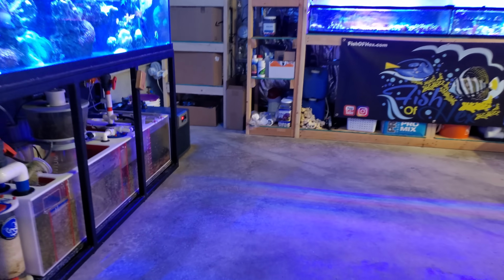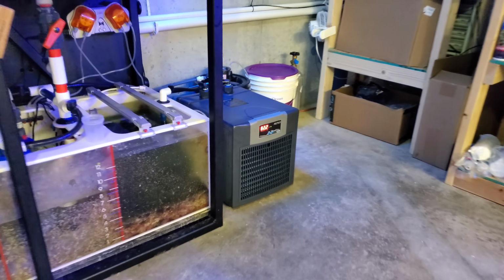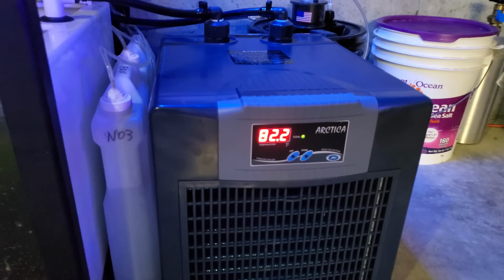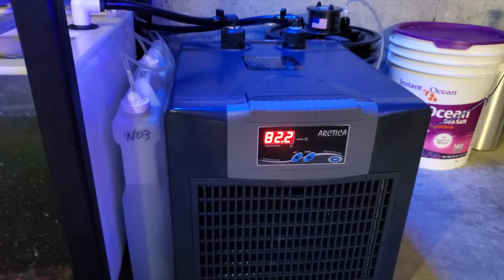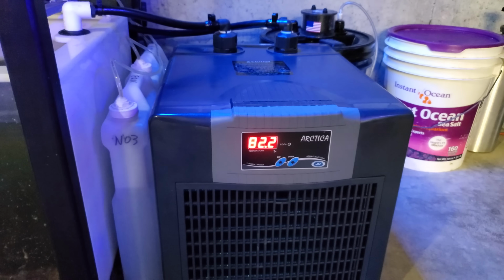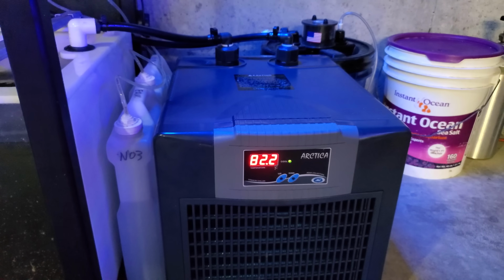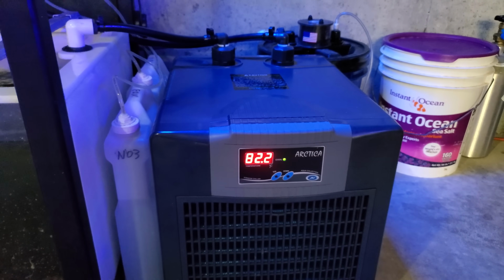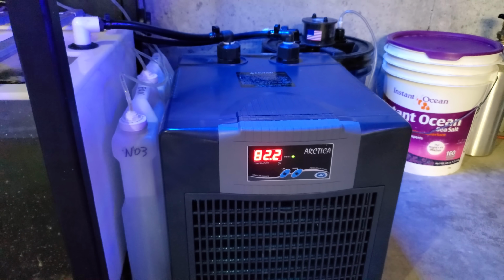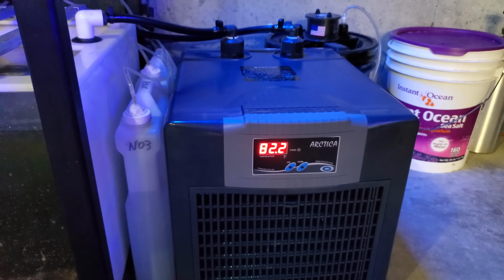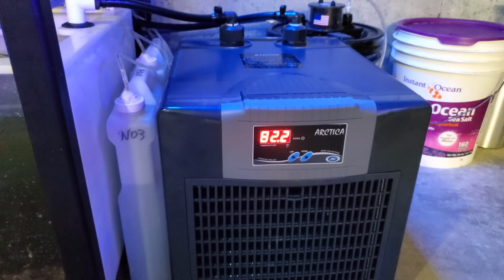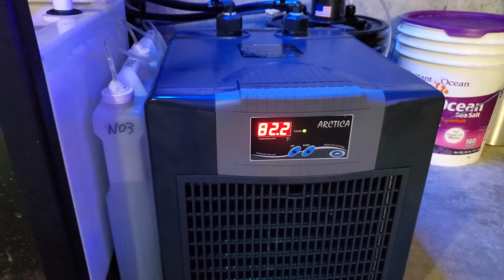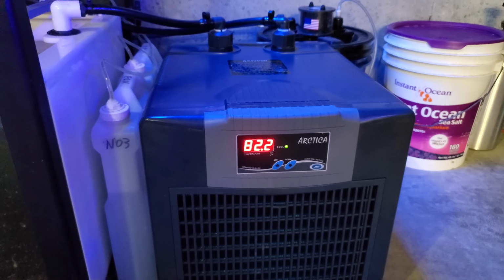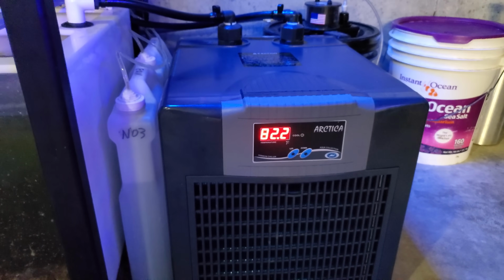Okay, so I just turned on the chiller, and you guys will see right off the bat that it says 82.2 degrees, the water that's going through the chiller right now. And I'm telling you, that is not correct. I verified with the HANNA temperature probe, which I'll show you guys in a second, and I also verified it with my Apex, and then I have just some random probes around here, and nothing's even close to that. So I don't know if this needs to be calibrated. I didn't see anything in the directions, and I will admit I kind of skimmed through the directions, so maybe it needs to be calibrated.